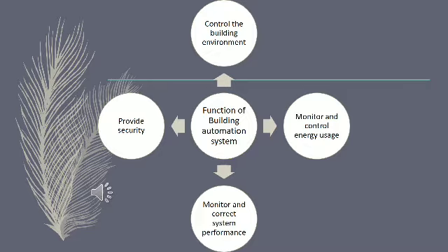This system attempts to automatically resolve the problem before getting a human involved. It will continually monitor and optimize its own performance, and the building manager only makes adjustments to the system when needed. Control the building environment. The building automation system will regulate the temperature, lighting, humidity and ventilation in order to keep the occupants comfortable. Occupancy sensors and schedulers reduce energy waste by adjusting environmental systems where they are not used.